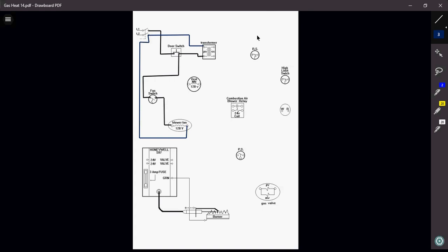Now, over time, with more experience and more training that you get, obviously it becomes a lot easier to know how things are wired and where things are supposed to be and where they're located inside a furnace. The only way you're ever going to get that experience is by physically doing it and getting in front of that unit and looking at the wiring, comparing your apples to your oranges. What do I have? Here's my wiring diagram. Okay, here's my wire. Here's my power coming in. Where does that wire go? Sit there and physically pull the wire. Does it go where the wire says it's supposed to go on the ladder diagram? Okay? So, that's what we just did here.